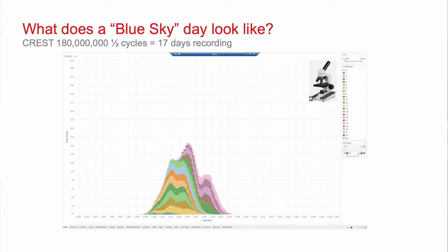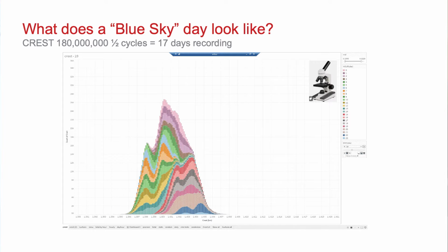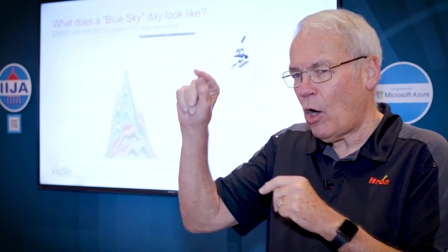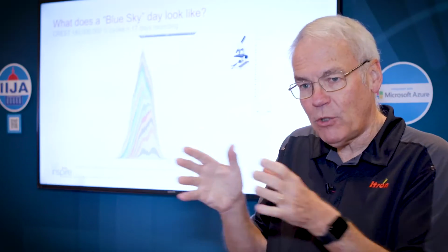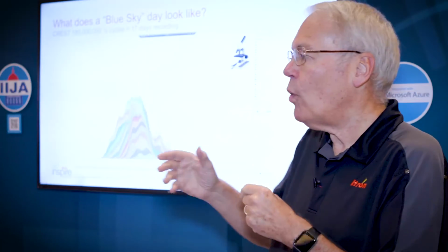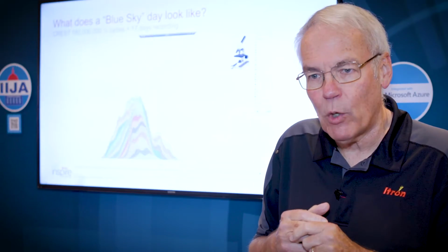So what Itron has done in the latest meters is we've enabled the waveform capture, the ability to capture that waveform in real time, 32,000 times per second. So this is actually an example of a utilities grid. We're constantly capturing and watching our measurements of that shape change over time. Because there's some natural changes. It's not always solid, but if we can figure out how much it's allowed to change, we can then detect anything that's outside of that band. So Itron has enabled the meters to record utility grids, this is a Midwestern grid, and determine what's normal and what's abnormal in the grid.